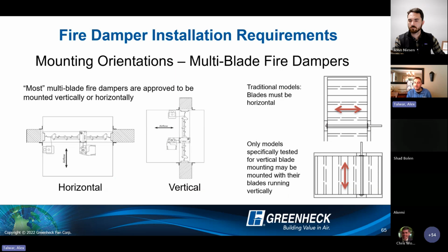One thing I did not mention with the multi-blade products, one thing we can't do is take them where the blades are running horizontally and rotate them 90 degrees so the blades are running vertically. We need special vertical blade products for that. We do have them, we do make them, but there's a little bit of a design difference. We'll put extra washers in them to help them pass the fire test and keep the blades in position.